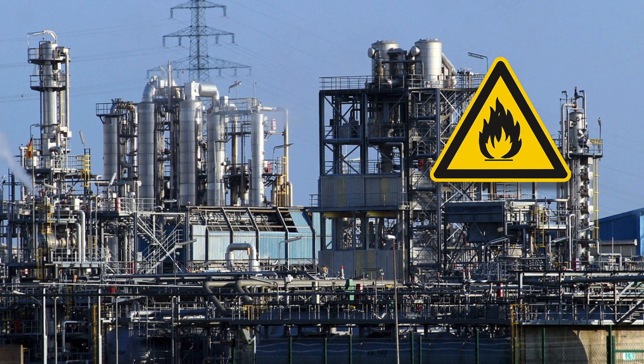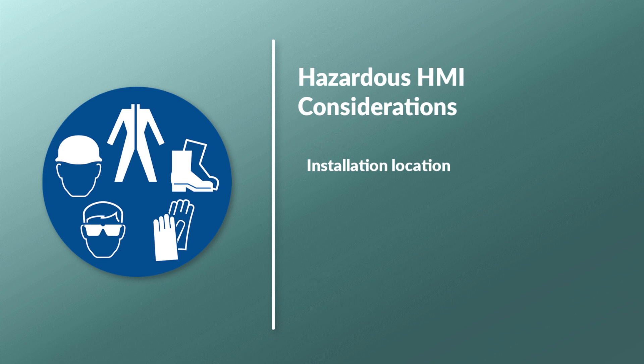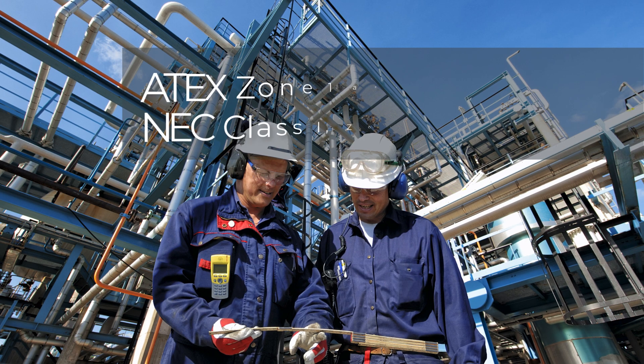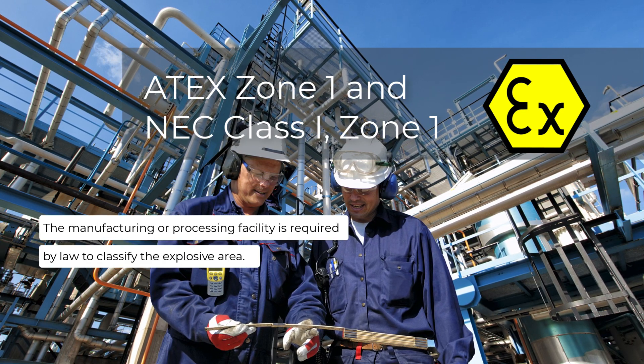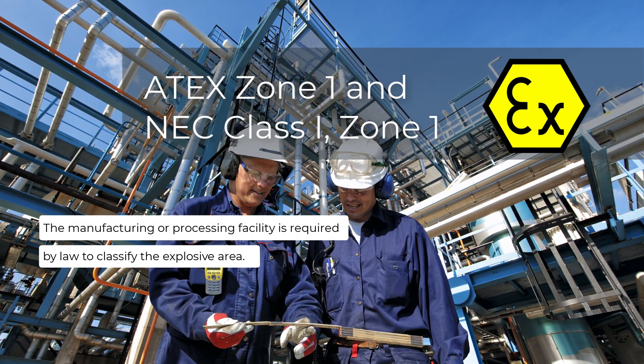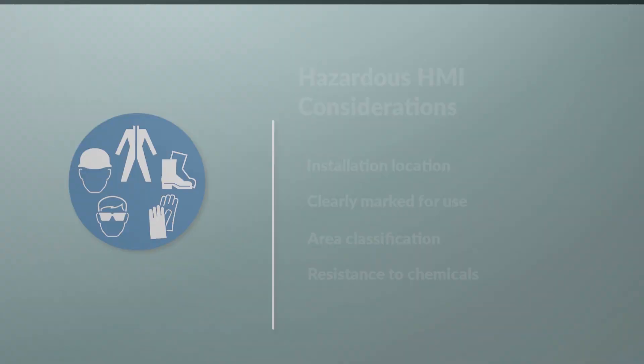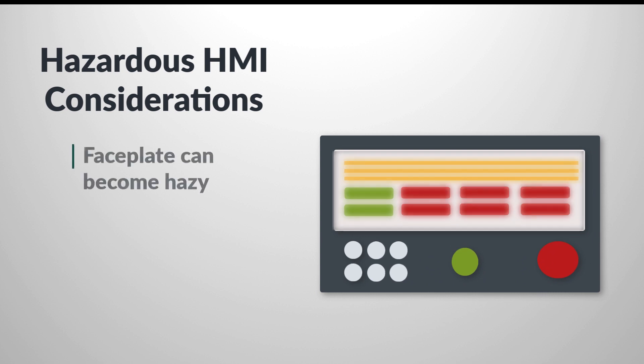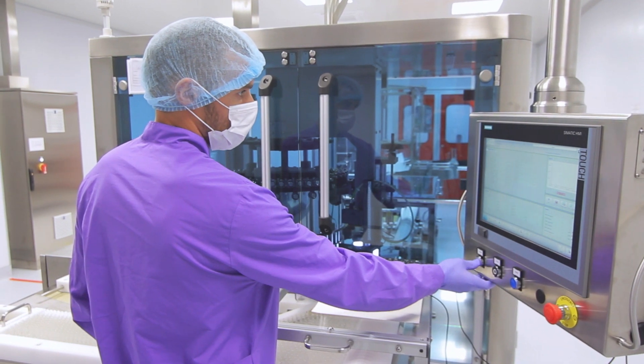Since an HMI is a possible ignition source when used in a hazardous area, consider mounting it in a safe area. If not, the HMI specified must be clearly marked with the certification for use and the area classification — for example, ATEX Zone 1 and NEC Class 1 Zone 1. The manufacturing or processing facility is required by law to classify the explosive area. The material used in the construction of the HMI also needs to be immune to any chemicals present in the atmosphere. If not, the display faceplate is likely to become hazy or the housing may soften. And personal protective equipment, such as gloves, may make it difficult to operate a small display, so a larger screen should be considered.